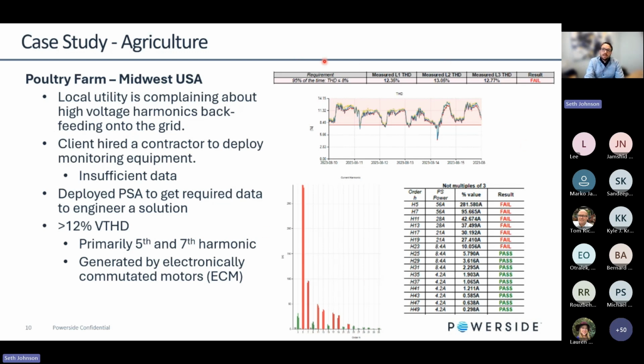And you can see here, this is for voltage. We needed to stay below 8% voltage distortion per IEEE 519, at the low voltage side of the transformer from the utility. And they were hovering in the 13% range, sometimes even higher, depending on the time of day, of course. And you may be wondering, okay, what is it that's causing these harmonics? We were wondering the same thing, which is why they gave us a detailed load list of what they had on site.